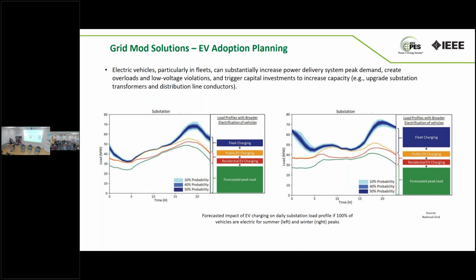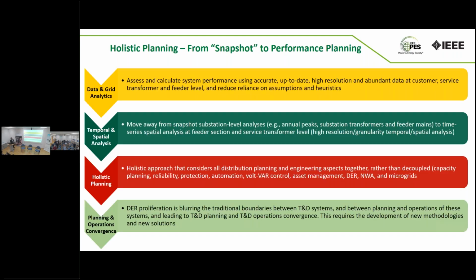So it's important to understand how to plan the grid with electric vehicles. Going back to planning, we need to move from what I call snapshot planning, the traditional way to plan the grid. In the past, we used to focus on making sure we could supply peak demand, which happens maybe one hour a year, and we'd focus on feeders and substations - what happens downstream didn't matter much, unless we knew some service transformers might be overloaded. But it was a snapshot in time, narrowly focused on key assets.